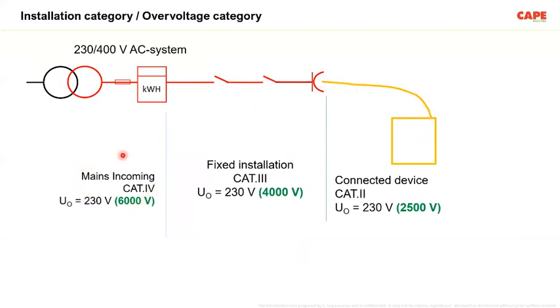Now, every electrical apparatus at the mains incoming must be of category 4, meaning a 230 volt device must withstand a minimum 6 kV voltage impulse. At the fixed part of the installation, category 3 means a 230 volt device must withstand a minimum 4 kV, or 4000 volt, impulse. Connected devices, such as apparatus which we use at our houses, are category 2. A 230 volt device must withstand 2.5 kV.